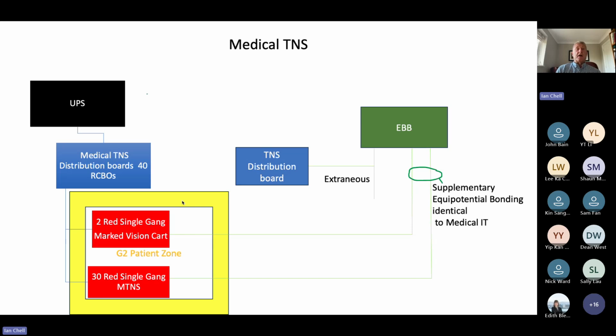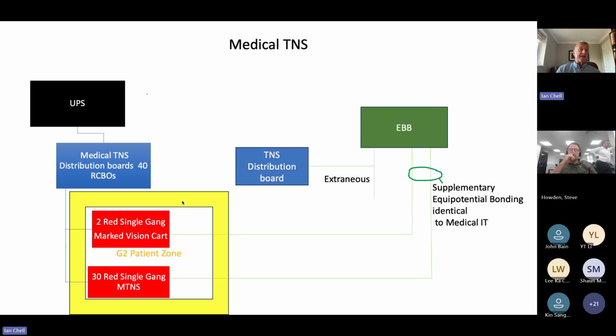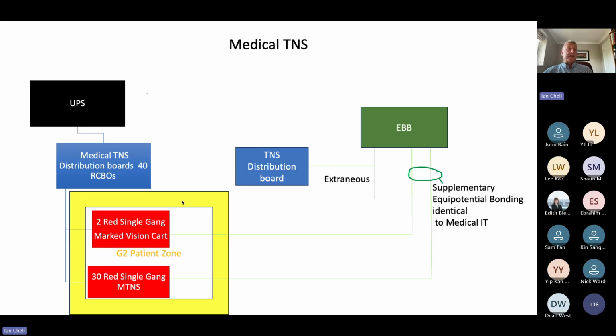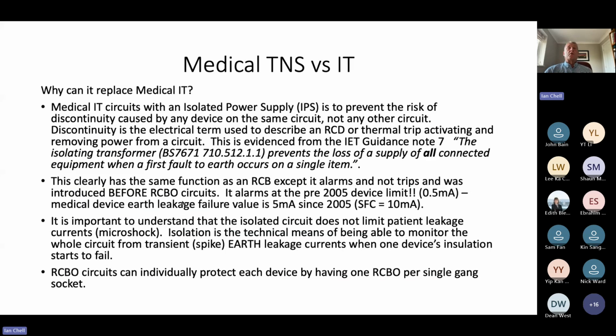Now, if you notice, all of these are wired exactly the same as medical IT sockets. They each have their own radial earth, supplementary earthing, going back to the EBB. If they're mounted on metal, then they are isolated from the metal conductive parts. So why can it replace medical IT? Well, as I've said before, medical IT circuits with an IPS is to prevent the risk of discontinuity caused by any device on the same circuit, not on any other circuit.